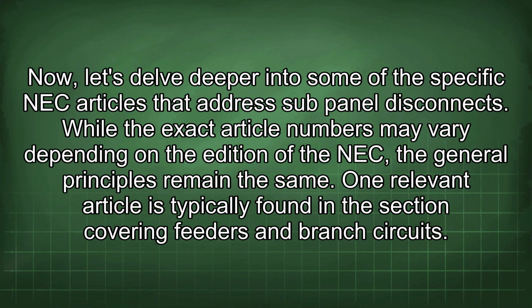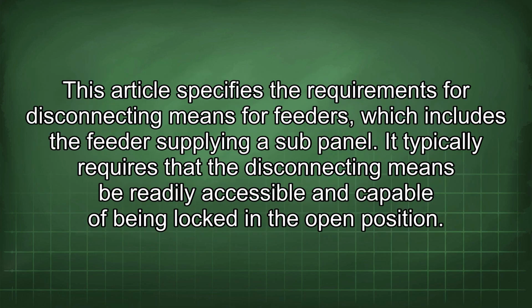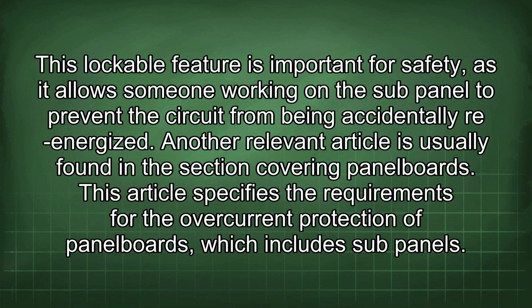One relevant article is typically found in the section covering feeders and branch circuits. This article specifies the requirements for disconnecting means for feeders, which includes the feeder supplying a sub-panel. It typically requires that the disconnecting means be readily accessible and capable of being locked in the open position. This lockable feature is important for safety, as it allows someone working on the sub-panel to prevent the circuit from being accidentally re-energized.